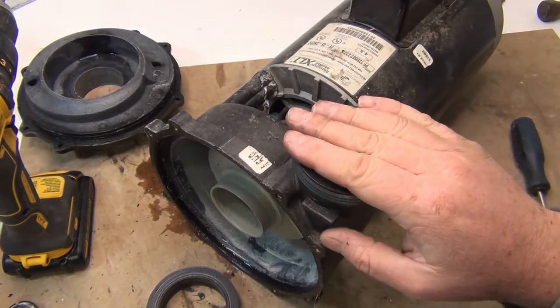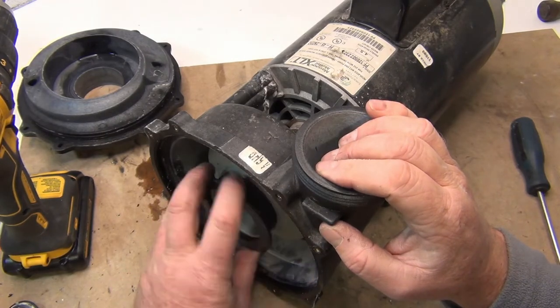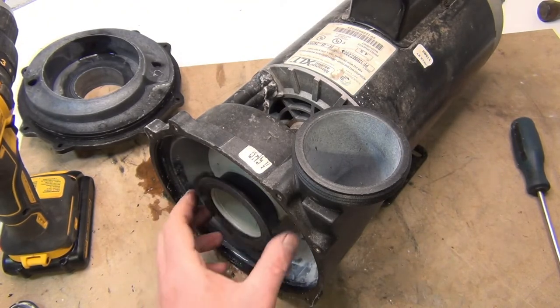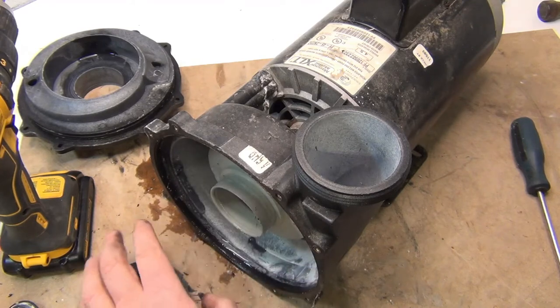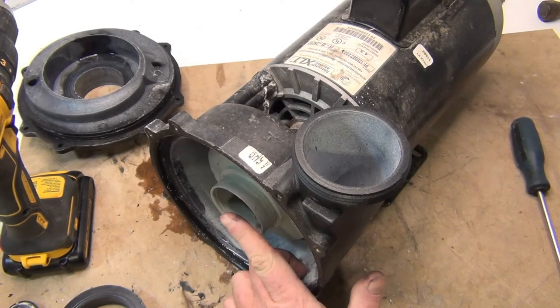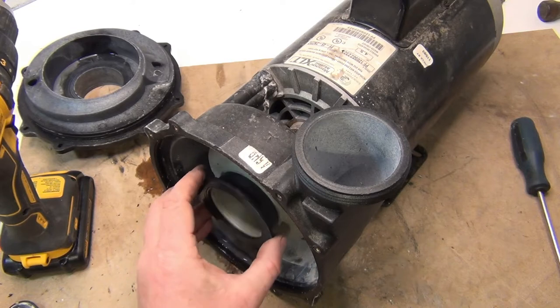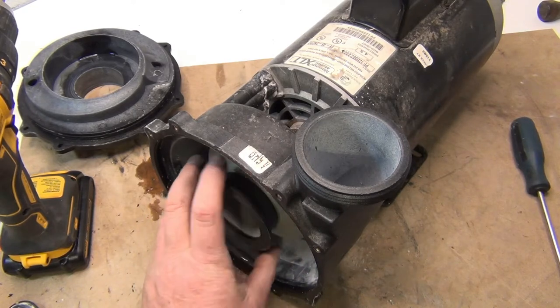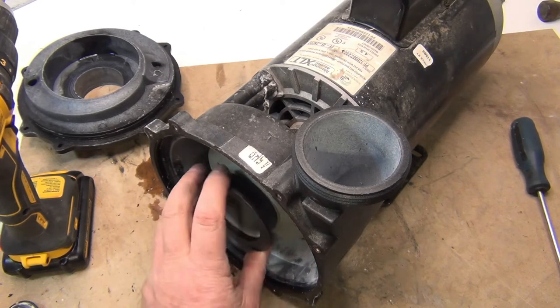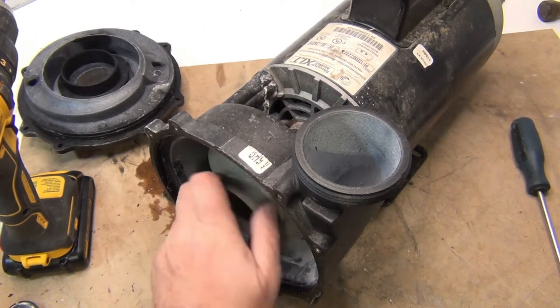The discharge is straight up and down. This piece fell out — it sits in there like that. There's a little space: if you just took this out and then put the front back on, this floats in there. Sometimes you can hear a whistling noise from it. Sometimes if these break — and they do break once in a while — you'll hear crackling and clicking because all the pieces are flying around.